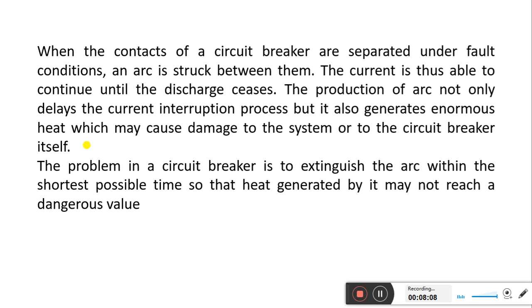So our main problem in this protection system is that when a circuit breaker is trying to open, there will be development of an arc between the contacts, and this arc tries to continue the flow of current and also generates heat in the space between the contacts. So we have to be very careful that this heat generated may damage the circuit breaker.